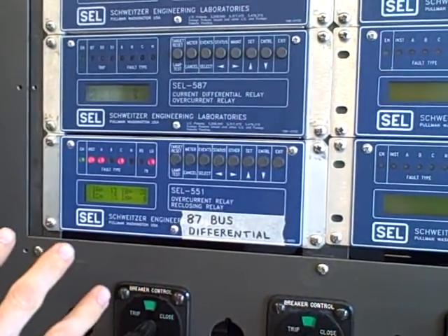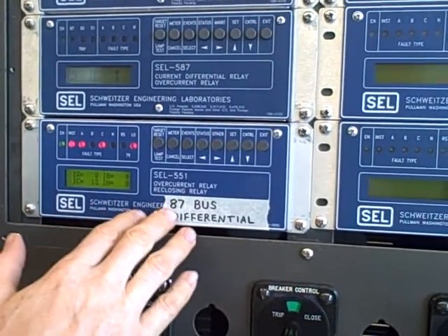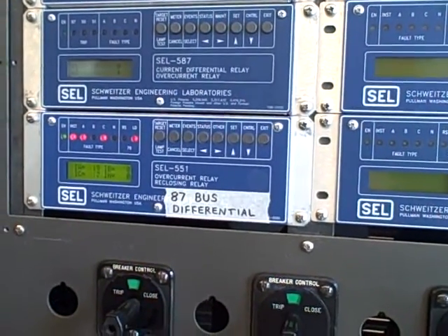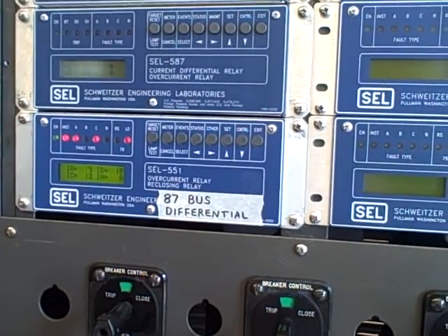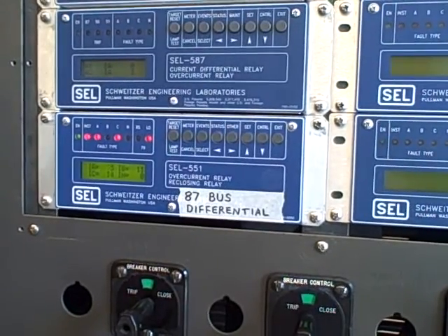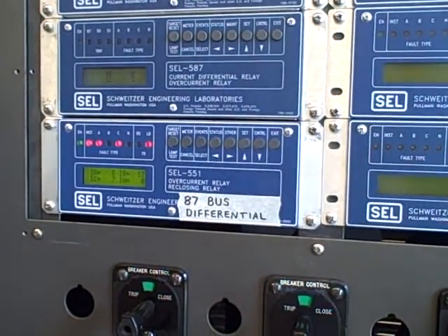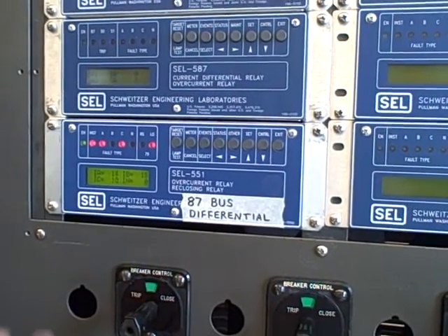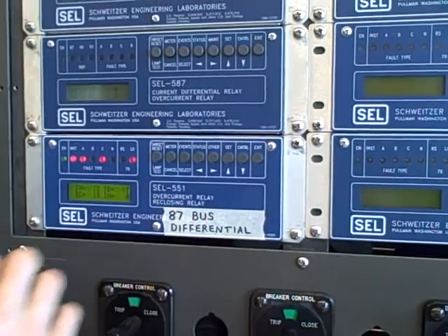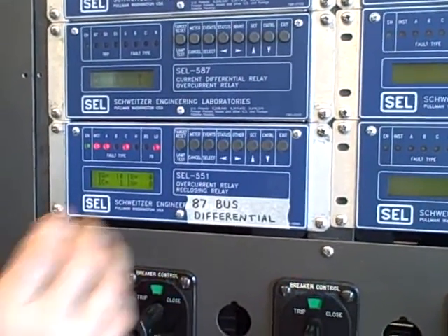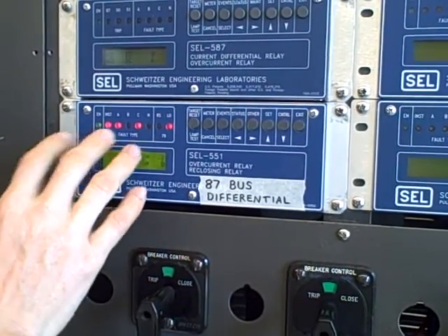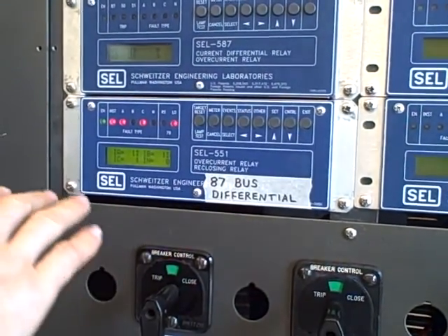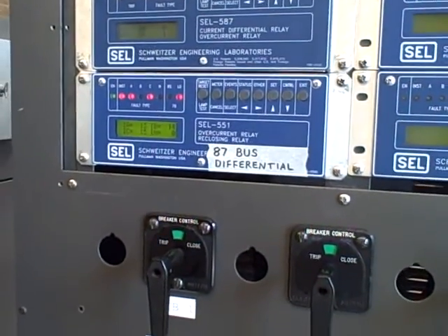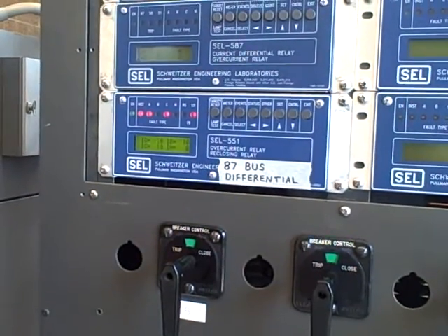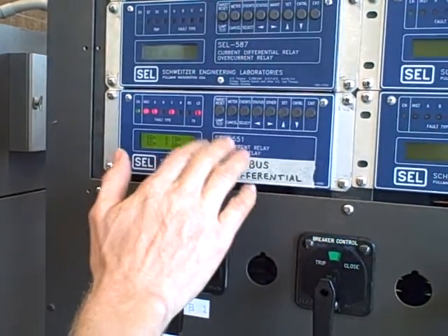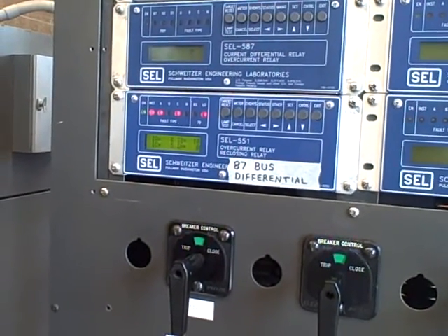Now, I should point out a feature here. This is actually not an 87 relay from Schweitzer Engineering Labs. This is actually an overcurrent relay that we have adapted to be an 87 relay. Why? Because I can't afford an 87 relay. They're very expensive. They're nice. I'd love to get one. Someday I will have one. What we've done right now is adapt a 551 model overcurrent relay to be a bus differential. We have configured this to only operate on instantaneous. There is no time function here, so it's very, very fast, and we set it for the lowest threshold possible in the settings of that relay. So in case anyone who knows about SEL products is looking at this quizzically, that's what's going on. We are using an overcurrent relay as a bus differential to demonstrate the concept.